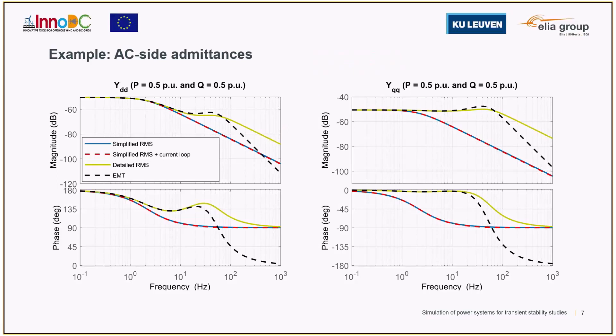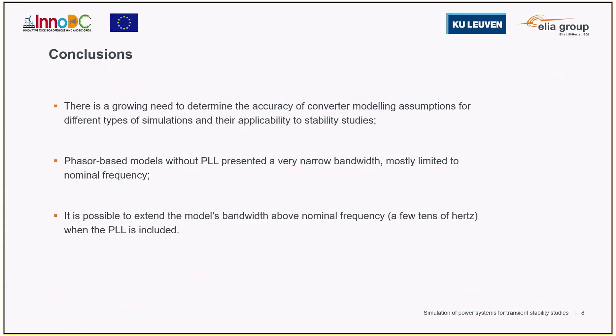The least accurate models are those that do not include the PLL dynamics — the simplified RMS models. These are only valid for frequencies very close to the nominal frequency of 50 Hz, as they start to diverge at very low frequency offsets. As a conclusion, there is a growing need to determine the accuracy of converter modeling assumptions for different simulation types. Phasor-based models without PLL presented a very narrow bandwidth, mostly limited to nominal frequency, but including the PLL extended this bandwidth above nominal frequency up to a few tens of Hertz.